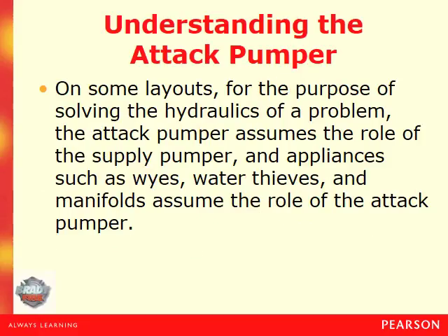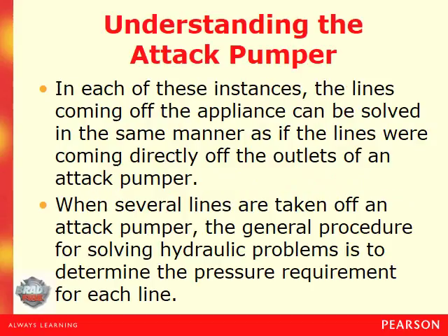On some layouts, for the purpose of solving the hydraulics of a problem, the attack pumper assumes the role of the supply pumper, and appliances such as wyes, water thieves, and manifolds assume the role of the attack pumper. In each of these instances, the lines coming off the appliance can be solved in the same manner as if the lines were coming directly off the outlet of an attack pumper.